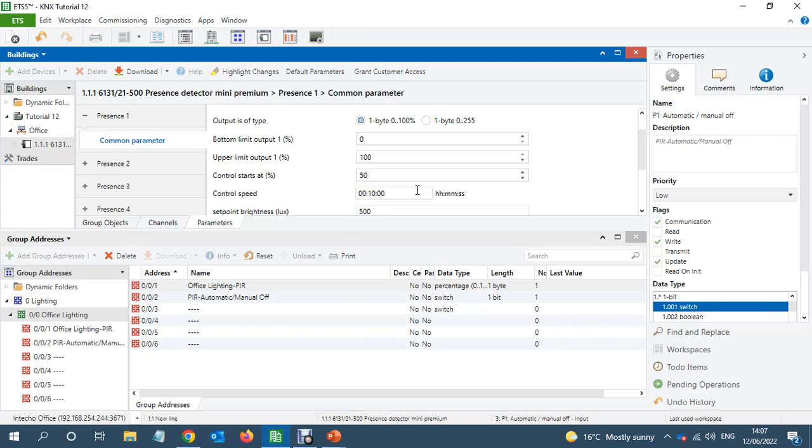Now in a case if someone walks in to go and turn out the lights, there are any blinds or something, and they walk in, the PIR comes on at 50%. And the process begins and that process will continue for 10 minutes. And when he is going out he wants to turn off the lights, there is a switch, he presses that switch, the light goes off. If he hasn't connected this object.